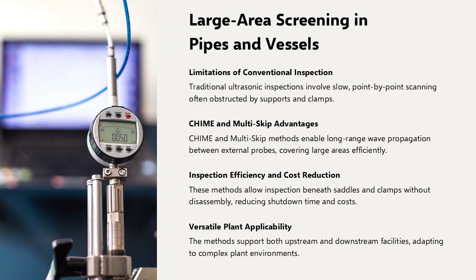As documented in CHIME field applications, this method provides coverage of the entire volume between probes separated by up to 1 meter or more. This capability enables operators to perform initial corrosion assessment quickly, identifying areas that require detailed follow-up inspections. The ability to inspect underneath saddles, pipe racks, or clamps without disassembly reduces shutdown costs significantly and improves inspection efficiency. Furthermore, this method supports both upstream and downstream facilities, offering versatile applicability across complex plant environments.